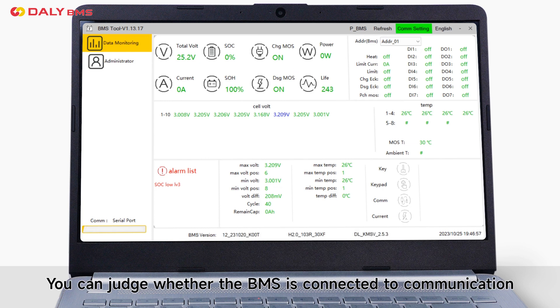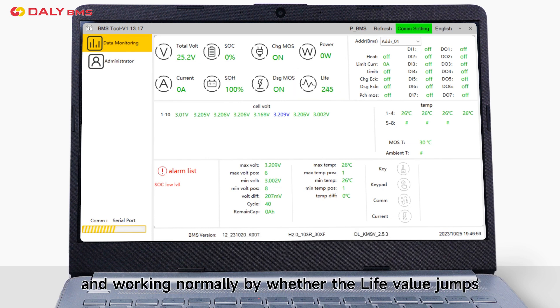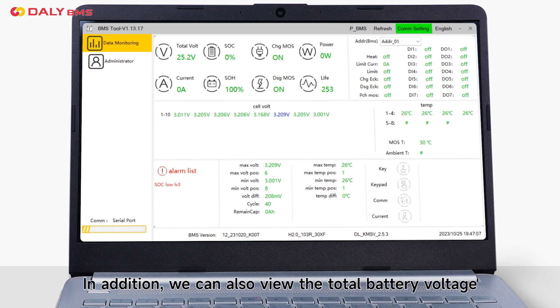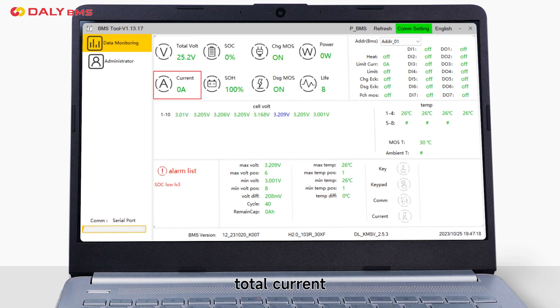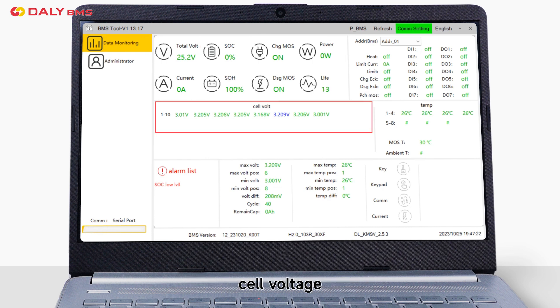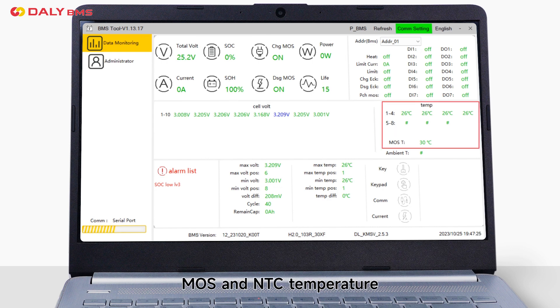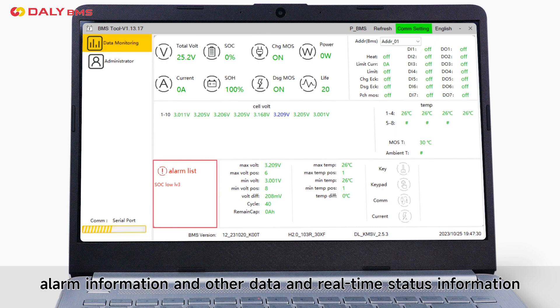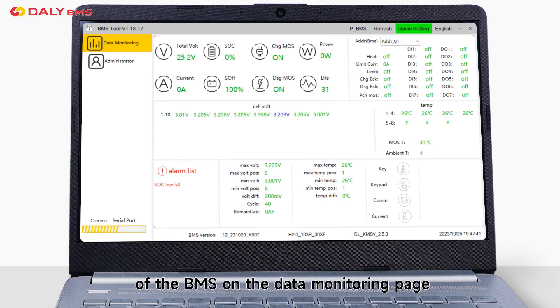You can judge whether the BMS is connected to the communication by whether the Life value jumps. In addition, we can also view the total battery voltage, total current, SOC, cell voltage, MOS and NTC temperature, alarm information and other data and real-time status information of the BMS on the data monitoring page.